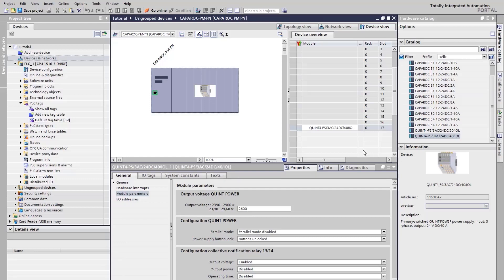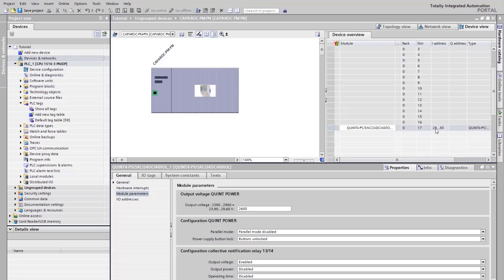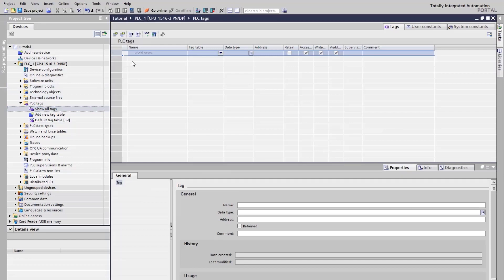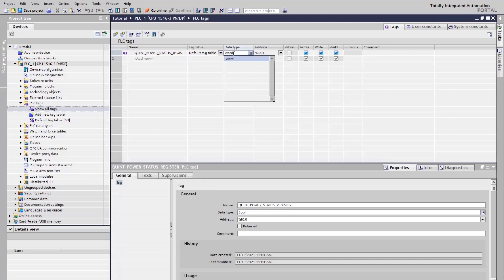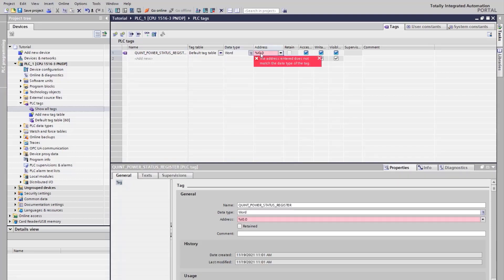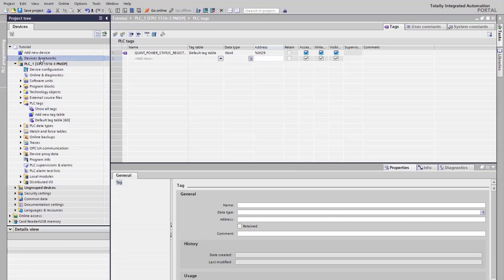To create a variable for the QUINT Power power supply status register, the I address of the power supply is needed. Find the I address in the device overview. Open the PLCTags section, add a new variable, choose a datatype word, and add the I address. Compile the project.